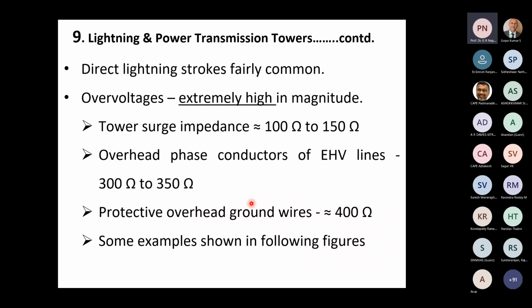Now, protection wires are overhead, tower top to tower top. Ground wires, of course, go in the form of a catenary. They maintain a minimum distance between the ground wire and the phase wire, considering various safety considerations. Therefore, a stroke can occur to the tower top or the overhead ground wire. Typically, if it hits the center of the overhead ground wire, that's the most dangerous thing. Again, the conductor is to be represented by its surge impedance. Since the overhead ground wires are single conductors, typically the surge impedance is 400 ohms.